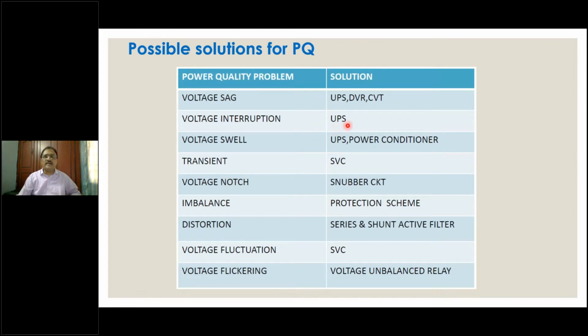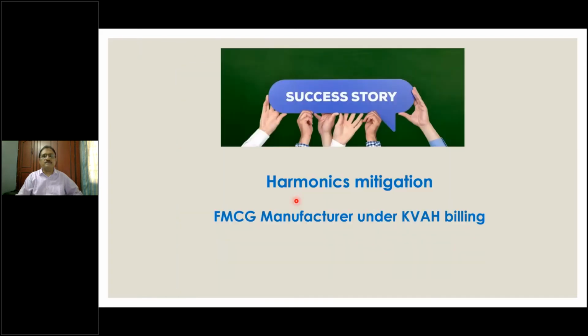UPS is a very popular choice, but UPS online particularly has a poor efficiency. It has the batteries and the AMC. AMC is almost 10 to 20% of the cost of the equipment year on year. So all these are prohibitively expensive. You will find that the DVR can do the solution, maintain the power supply adequately, and still be less than 25% of the losses of the UPS. So new idea maybe, I want you to think on it, develop your understanding and go forward.